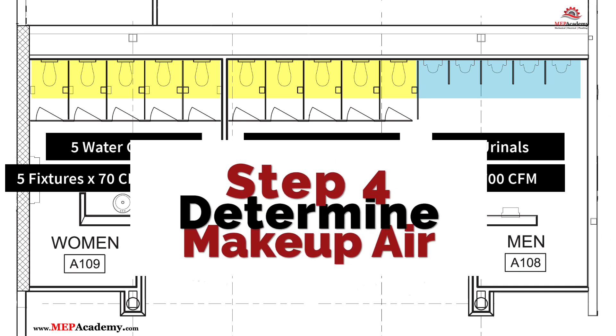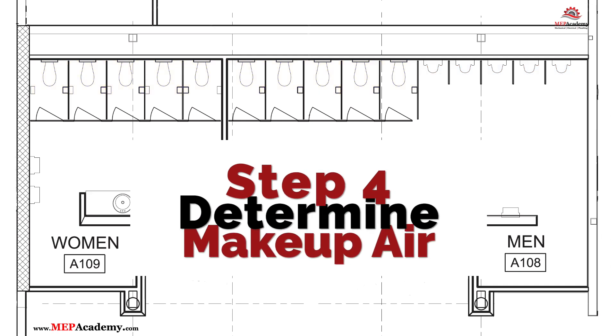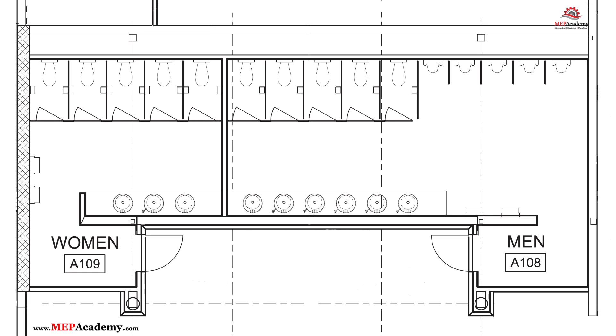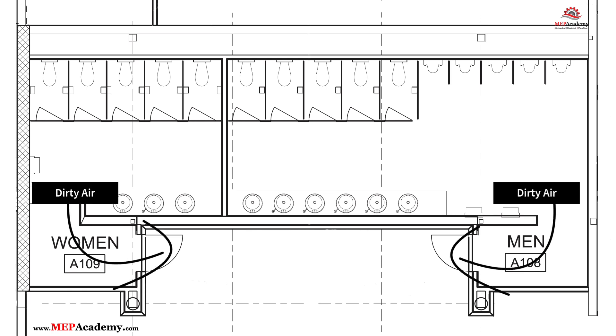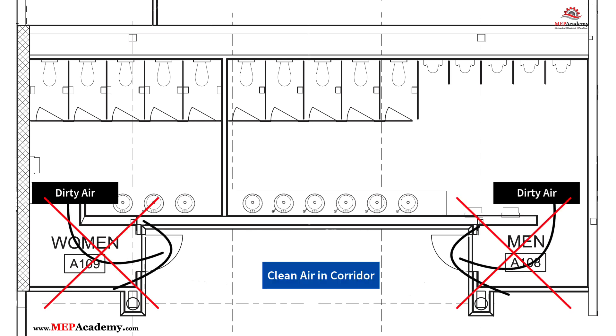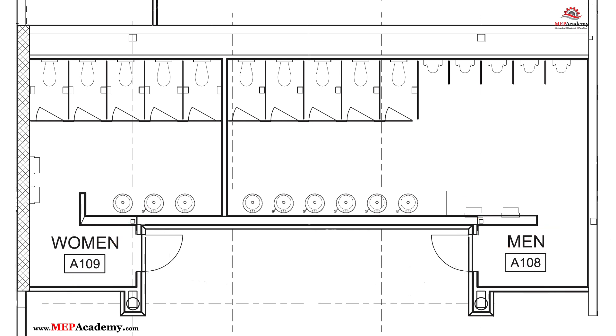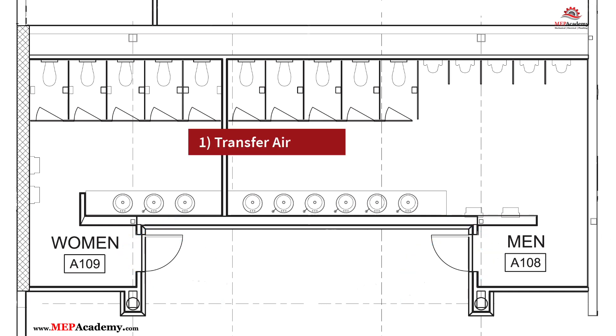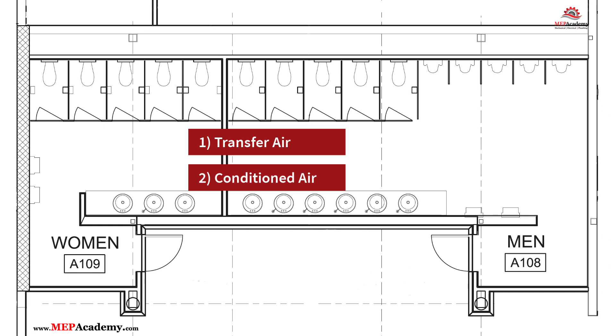Step 4: Determine the exhaust makeup air method. Providing makeup air for exhausted air is essential to maintaining proper pressure balance. ASHRAE recommends ensuring air doesn't flow from dirty areas into clean spaces and maintaining negative pressure. Common makeup air methods include: (1) transfer air — air from adjacent spaces flows in via door undercuts or grills; (2) dedicated conditioned air supplied directly through the HVAC system; and (3) a combination method — a mix of transfer and limited conditioned air.